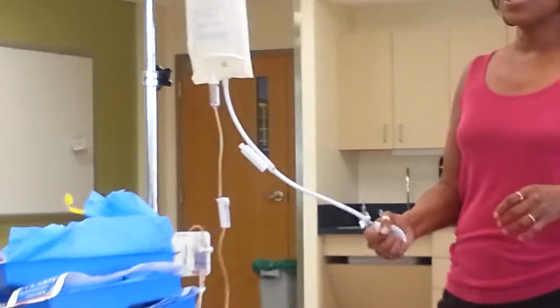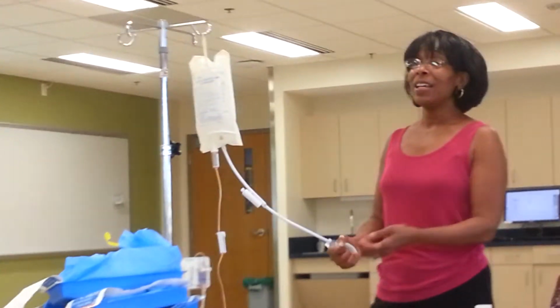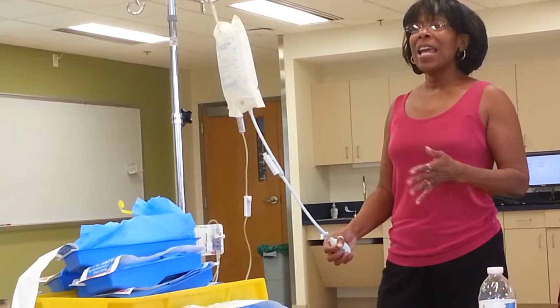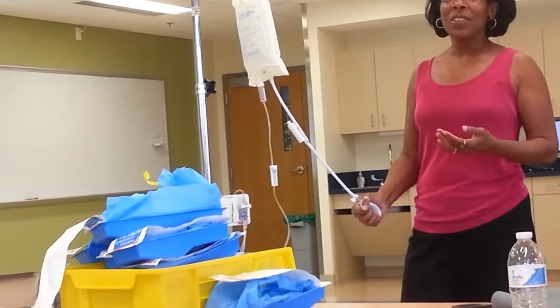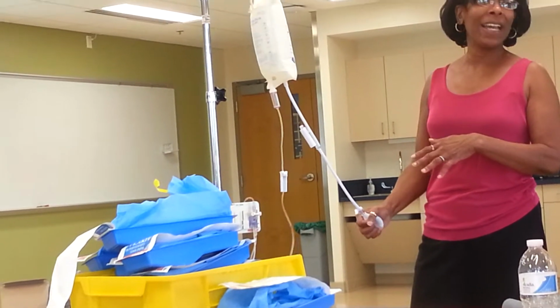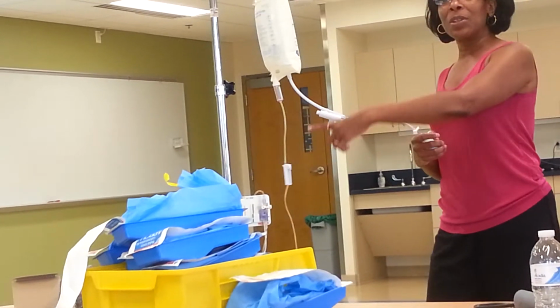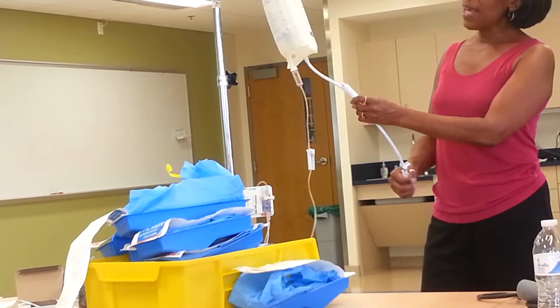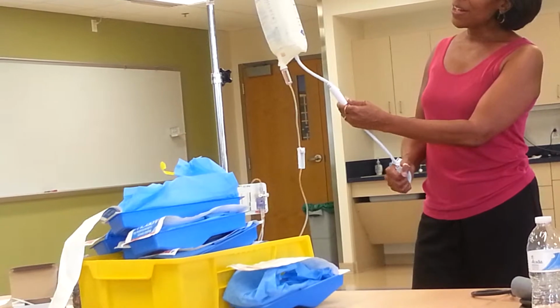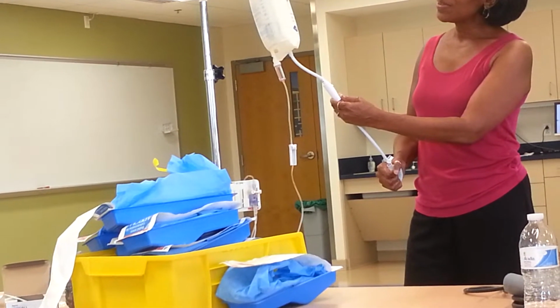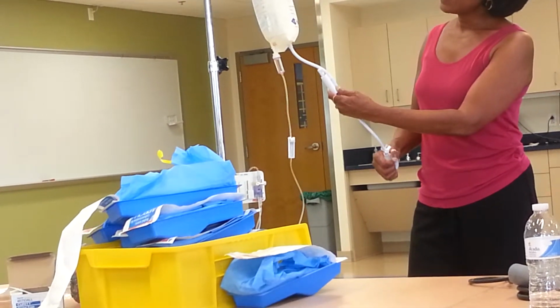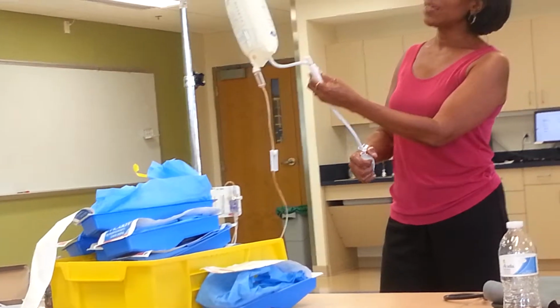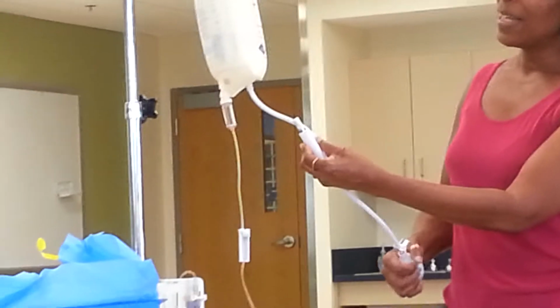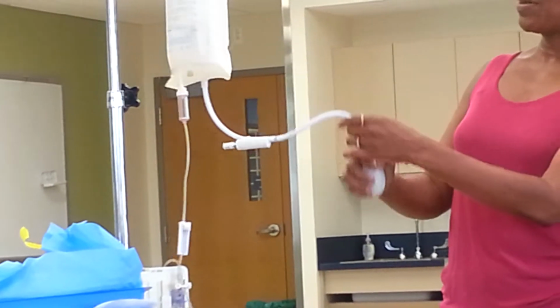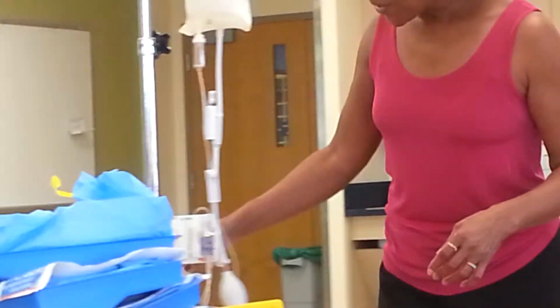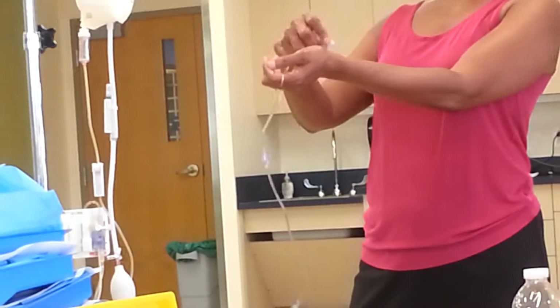Now the reason it's 300 is because remember the catheter is in the person's artery. Our blood pressure is like 120 over 80. So we've got to have that pressure pushing against that higher than what it should be. So usually 300 is plenty high to keep that blood from backing up all through the tubing. So you just keep pumping that up till it goes. It'll show 300, and then it also shows a green area too. There's 250. Keep going, and then a green area. Can you see the green coming up? That's 300. 300 millimeters of mercury, and then you lock it by turning it up. So now it's ready to go. The catheter will be here. Just connect onto the patient.